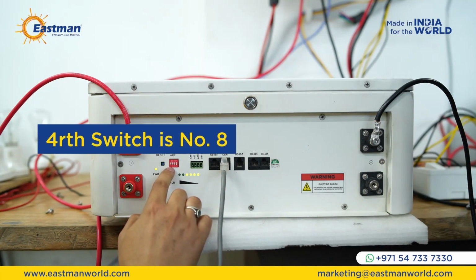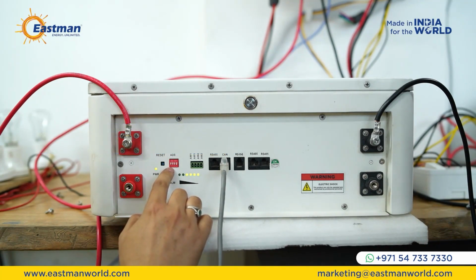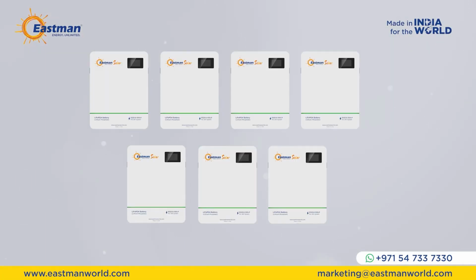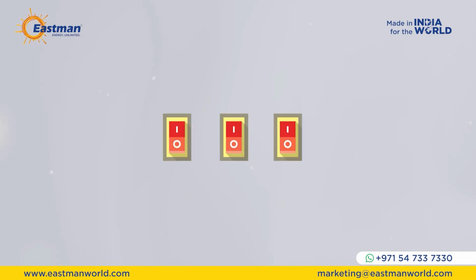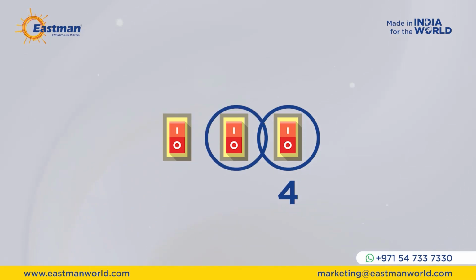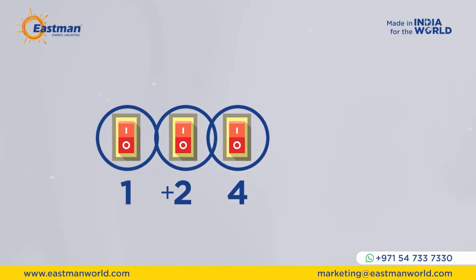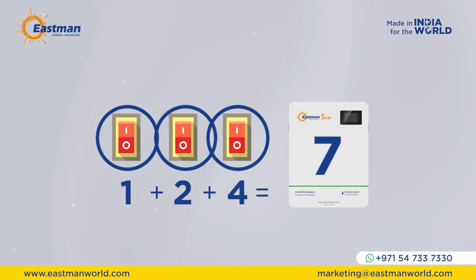This way we can connect from 1 up to a maximum of 15 batteries in parallel. For example, if we want to connect 7 batteries in parallel, we turn on the first 3 switches: the third switch is numbered 4, the second is 2, and the first is 1. Adding these 3 gives 7.